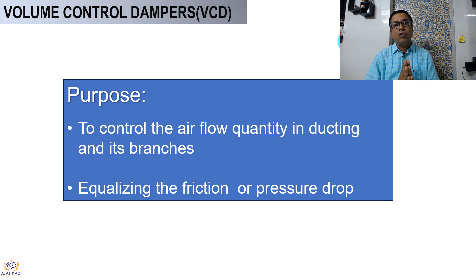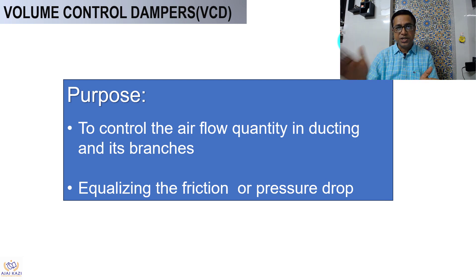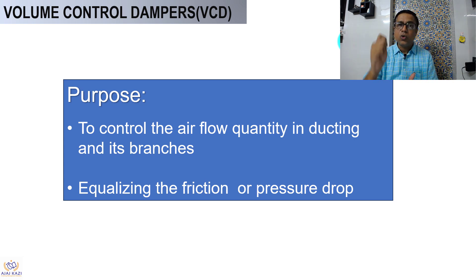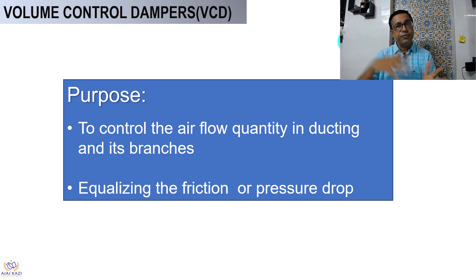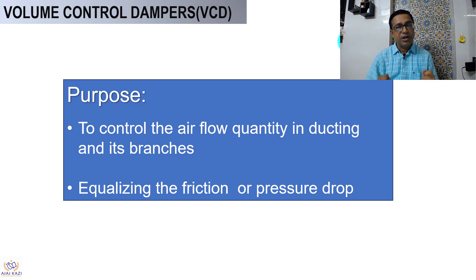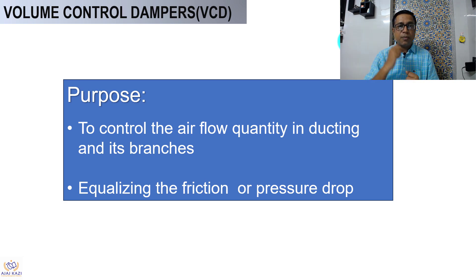The first damper we are going to talk about is the Volume Control Damper, generally called VCD. The purpose of this damper is to control the flow — the air quantity in the ducting and its branches — and also to equalize the friction and pressure drop within the duct.